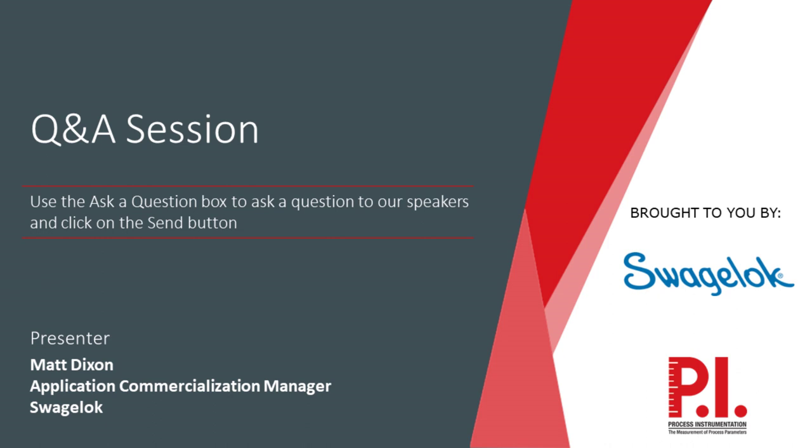Okay, thank you. Our next question asks, does the operator have to wait by the sampler while the ammonia sample evaporates? No, they do not. That would be an awful waste of somebody's time to sit there and watch ammonia boil away. So the sampler, as I mentioned, typically takes about 2 hours, and there are some relay outputs that it has, so you can monitor that remotely. Once it's done, it will give a remote signal to let whoever know that it's time to come back and take the reading.